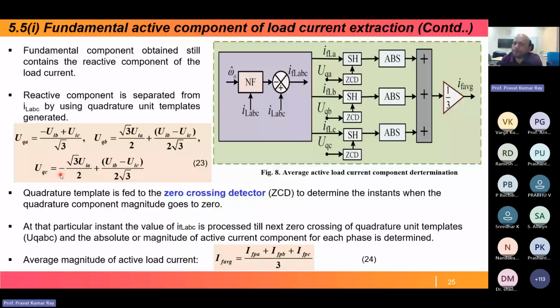Now the quadrature template is fed to the zero crossing detector. What it will do is determine the instant when the quadrature component magnitude goes to zero. Our objective is to remove this reactive component, so whatever UQA, UQB, UQC we find from equation 23 is fed to the zero crossing detector, which determines the instant when the quadrature component magnitude goes to zero.